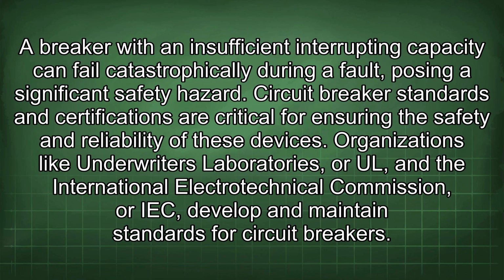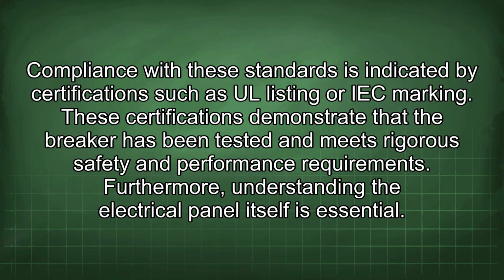Organizations like Underwriters Laboratories, or UL, and the International Electrotechnical Commission, or IEC, develop and maintain standards for circuit breakers. Compliance with these standards is indicated by certifications such as UL listing or IEC marking. These certifications demonstrate that the breaker has been tested and meets rigorous safety and performance requirements. Furthermore, understanding the electrical panel itself is essential.